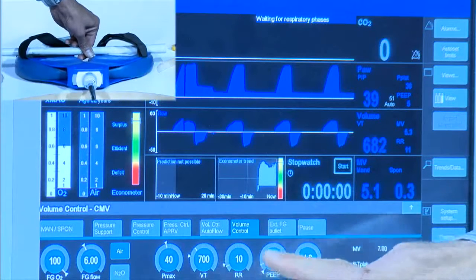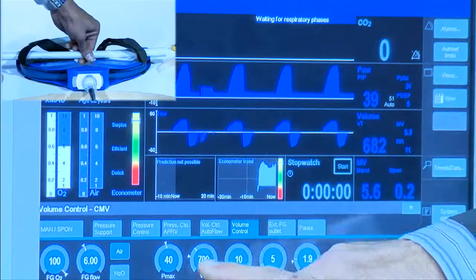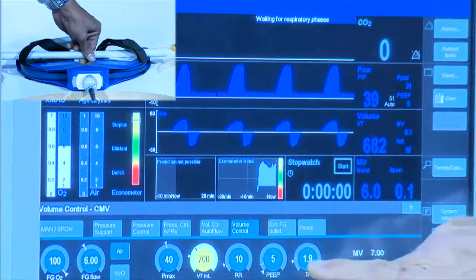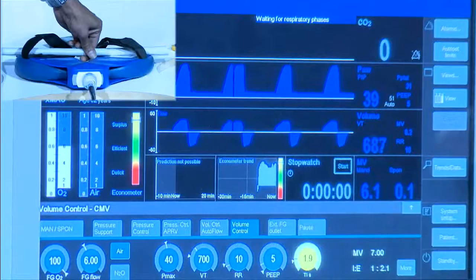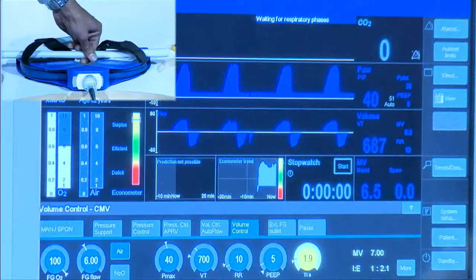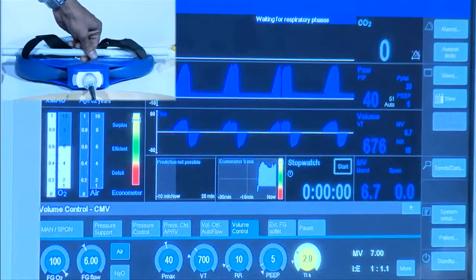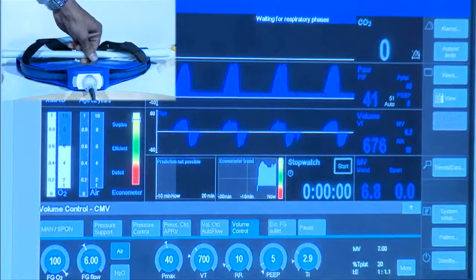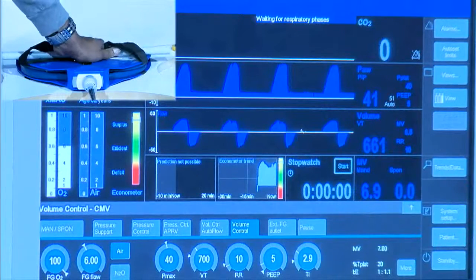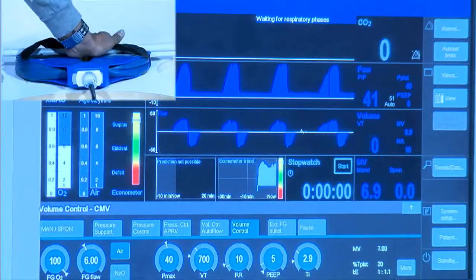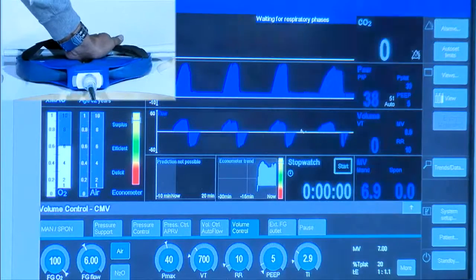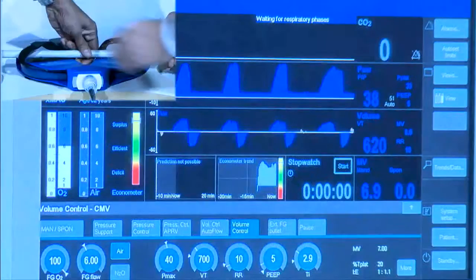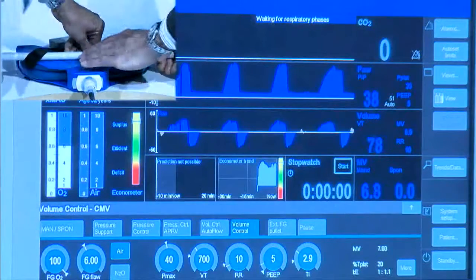What we could do, and achieving the same minute volume at a much lower pressure, let's just see what happens if I make the I:E ratio 1:1. So that's a pressure of 40. I'll only do that for now, and we'll just see what happens. I try to keep that constant. I know it's difficult, but just not more or less. I'll tell you what we'll do. Let's put the handle in the middle, up here. Yeah. Okay? Just keep that constant.